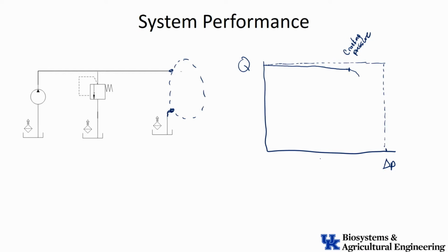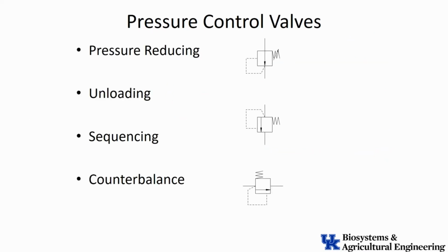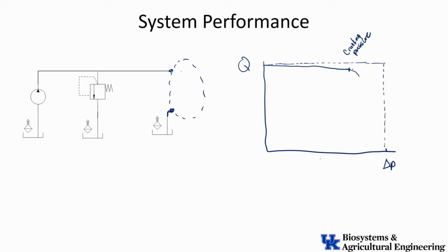So this is where this relief valve in the system over here starts to open to protect the system and allow flow to go out. So now, as the flow goes, I advance the slide there. So let me come back. As the relief valve opens and the pressure gets higher, I get more and more opening on that relief valve until the system will look something like that, till my pressure gets up to the maximum, and all the flow then that's coming out of the pump is going through the relief valve.